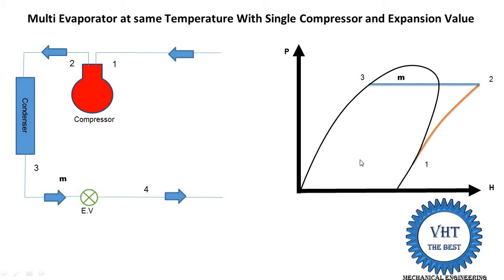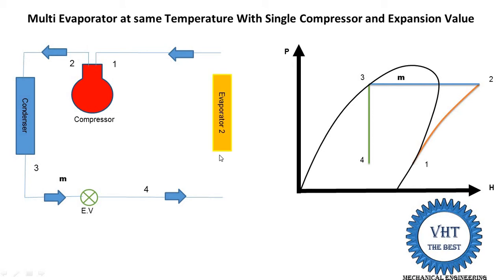Since enthalpy is on the x-axis, we draw a vertical line downward from point 3 — downward because pressure is reduced. When we take the projection of the 3 to 4 line on the x-axis, h3 equals h4, confirming they are the same. At point 4, the state of the refrigerant is low pressure, low temperature, liquid refrigerant.